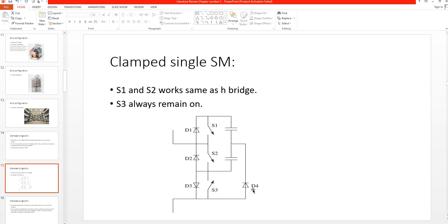When the arm current is negative — current flowing out of the submodule — D4 is in the path, and the current exits through D2. In this case, only one capacitor is available, meaning only half of the voltage is available to block the AC side fault current.